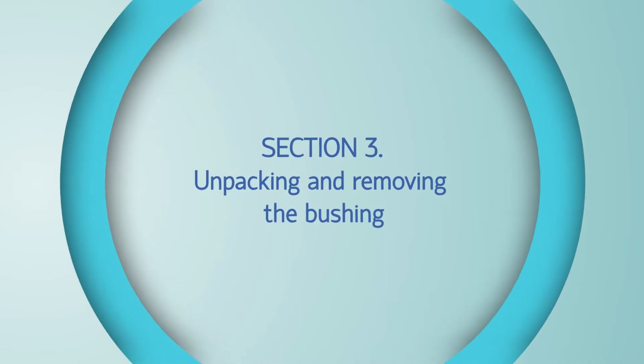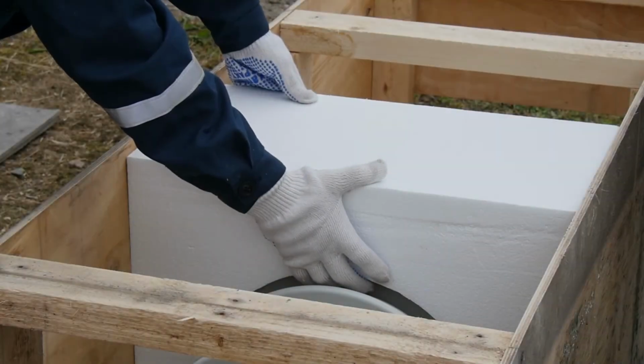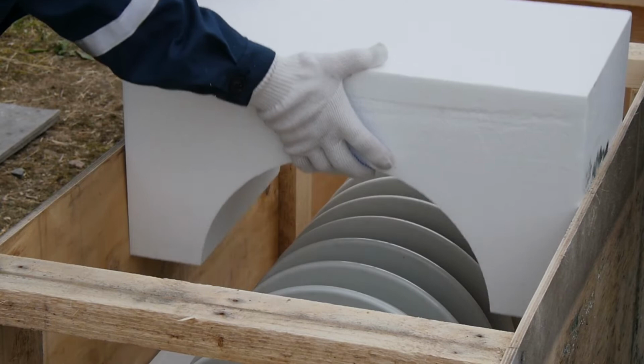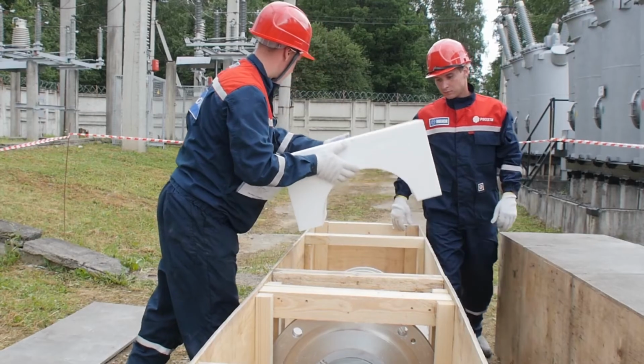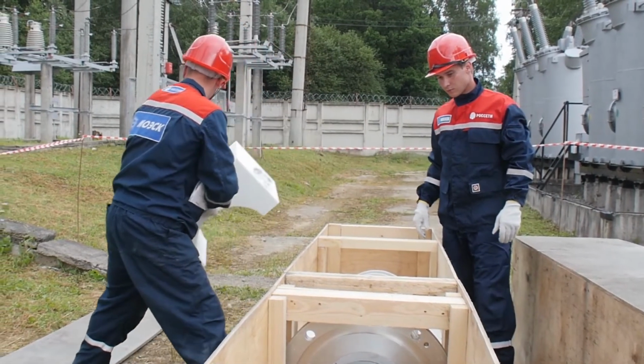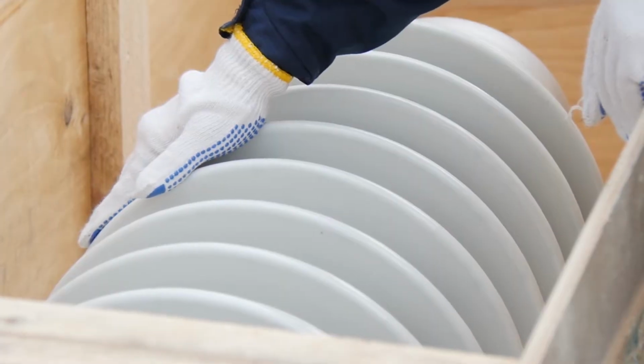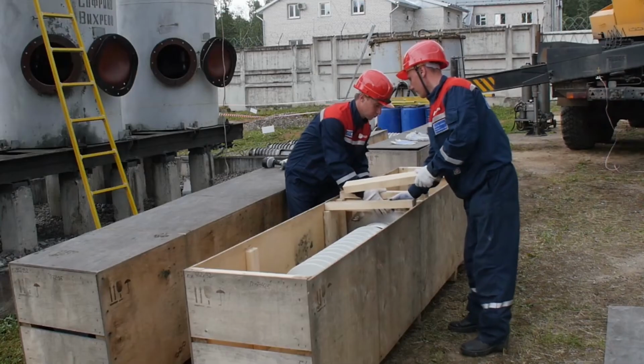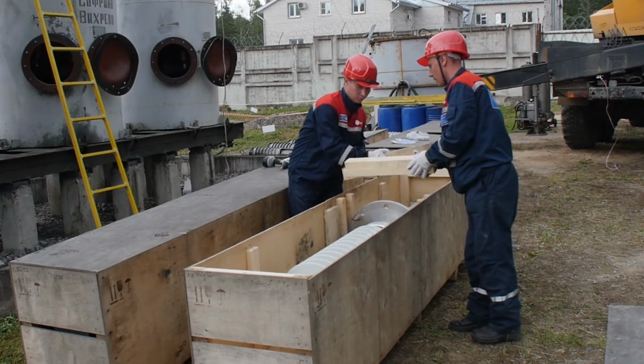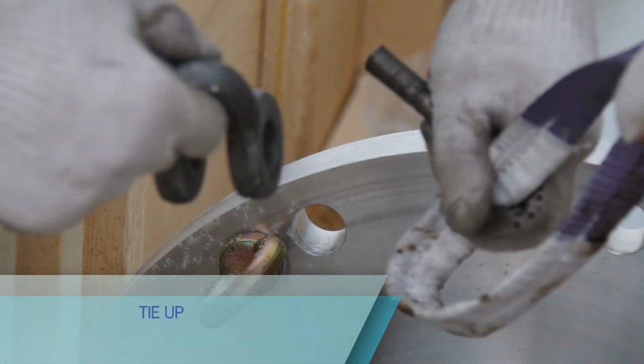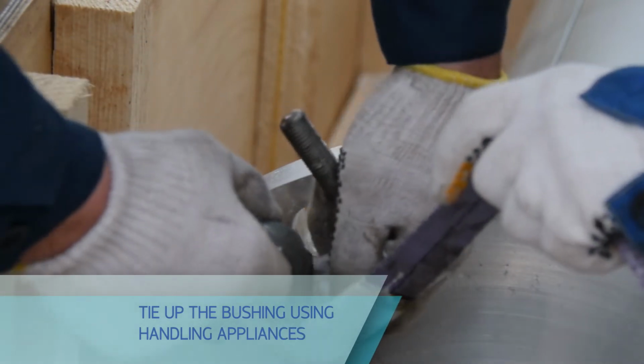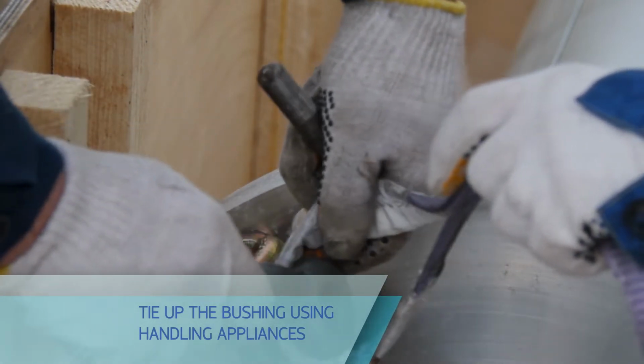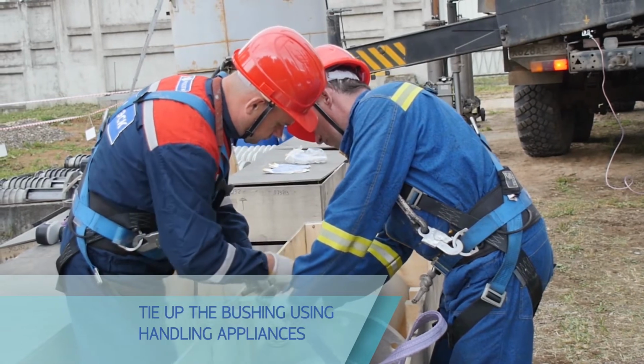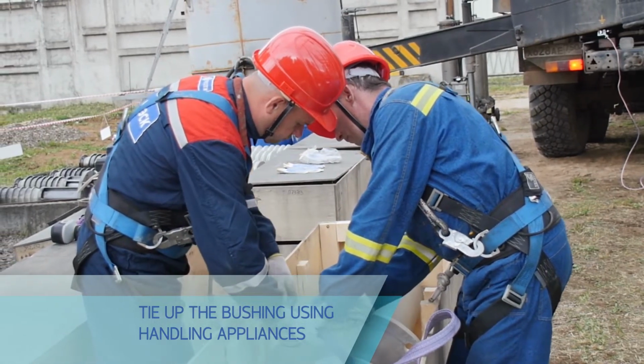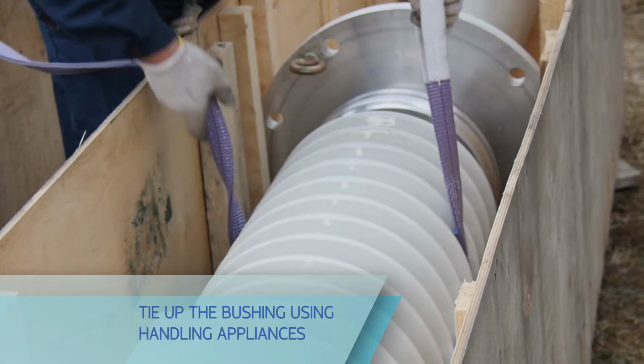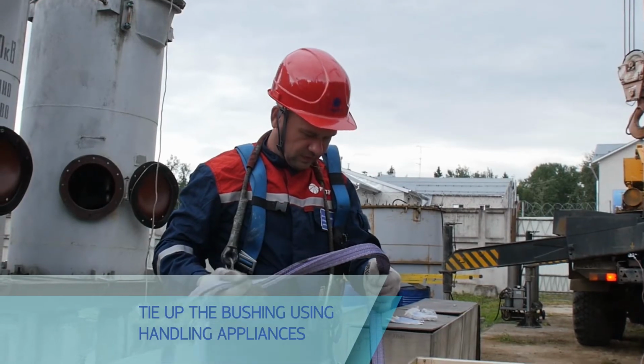Unpacking and removing the bushing. Remove polystyrene foam supports off the bushing top and put them in a stable place next to the package. These will be used for setting the bushing horizontally after removal. Release the bushing from all the fasteners inside the package. Tie up the bushing using handling appliances on the coupling. These may be represented by lugs or eye bolts of required capacity. Tie up the bushing using soft slings to avoid damage to porcelain housing according to a scheme shown in the operation manual.